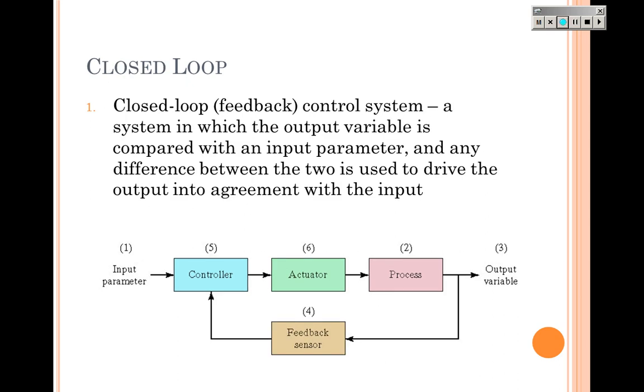Closed loop control means there is feedback, and when there's feedback there must be a sensor. The system doesn't necessarily have to correct the problem — it may simply shut the line down and alert the operator. Feedback can come from many sources: a limit switch, a thermocouple, a phototransistor, a photoresistor, a scale, or an optical scanning machine. The key difference between open and closed loop control is feedback.